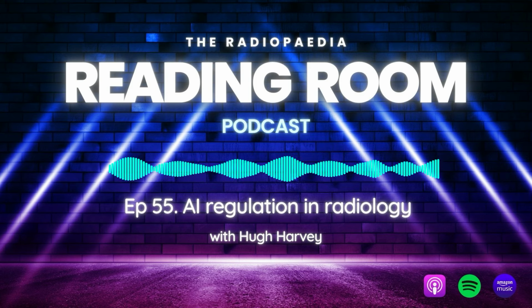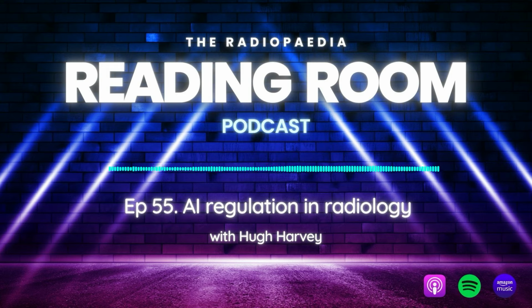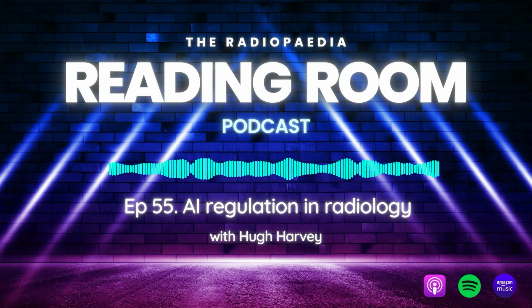So you need to follow that process from conceptualization, scientific validity, analytical validity, clinical validity. And then post-market, vendors need to conduct post-market surveillance and clinical follow-up. Surveillance is monitoring the market for adverse events of your device or other devices. Post-market clinical follow-up is doing meaningful audit and assessment of the performance of your device, measuring that and reporting it back. All of that information forms a clinical evaluation report.